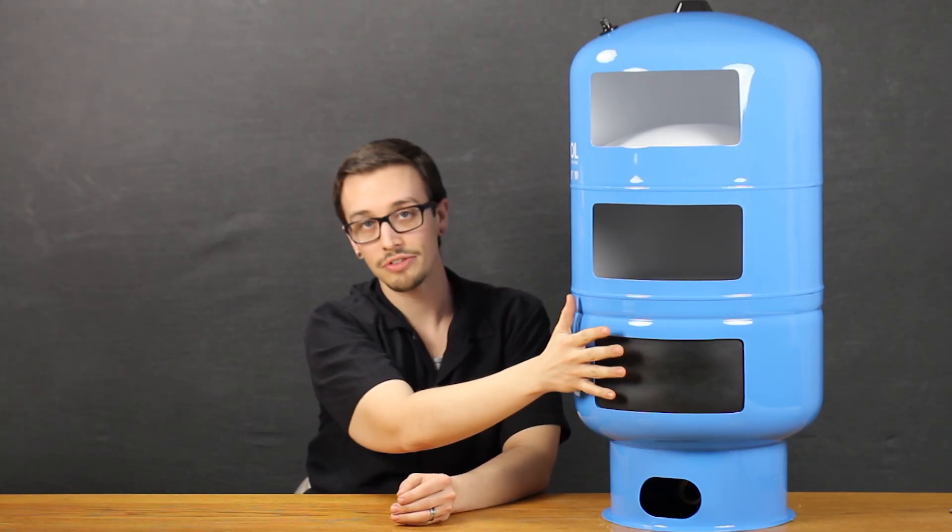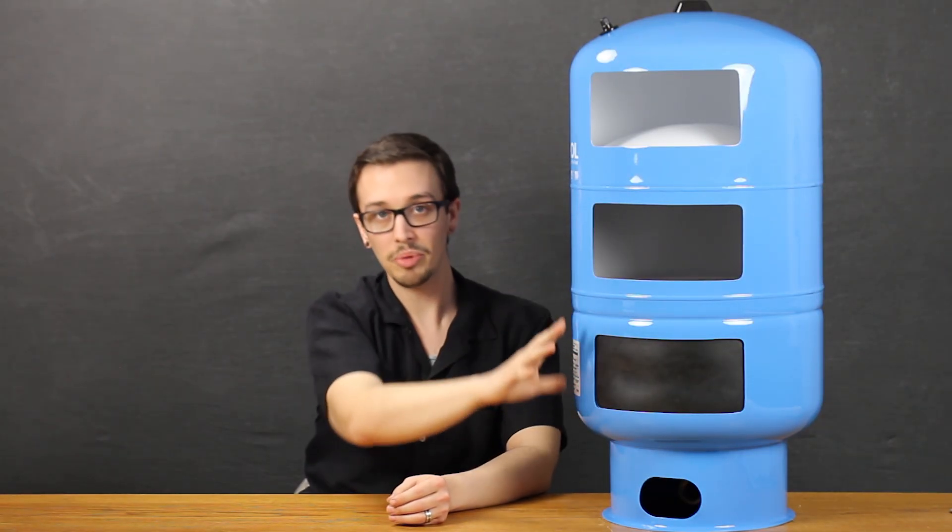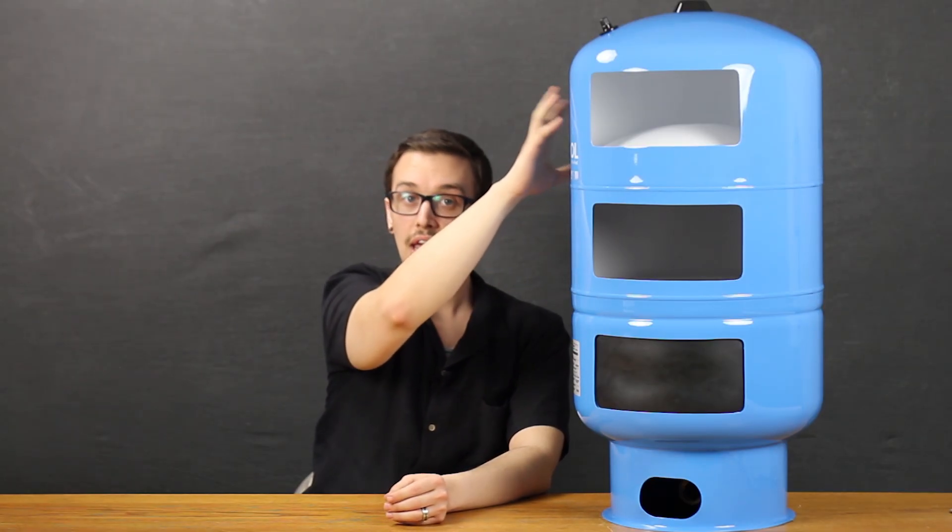Now, just to give you an idea, we have a pressure tank on the side of me here that has been cut out to showcase how it works. Now, the lower section of the tank is where the diaphragm is. And this weld here is essentially the line that marks the top of the diaphragm. As the pressure tank fills with water, this diaphragm expands upward and this area becomes filled full of water.